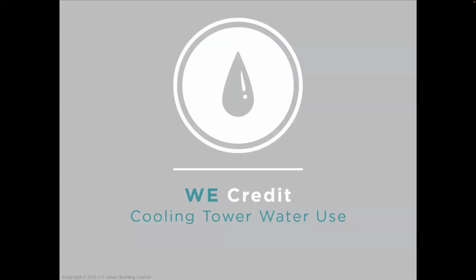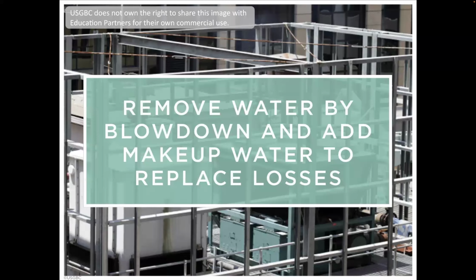All right, so cooling tower water use. Again, what a cooling tower is: if you're using what we call process water, you're using chilled water to cool your spaces. So they usually have these things called chillers, usually in the basement spaces. And in order to reject the heat from the building, they use a cooling tower. There's a couple of water loops, but ultimately there's a loop that takes the heat of the building and rejects it through the cooling tower.